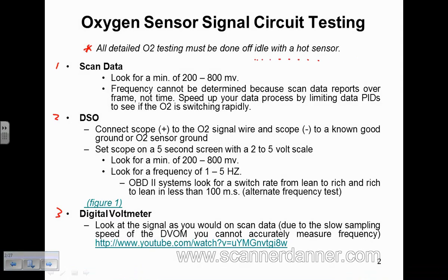Let's say here's your 800 millivolt line, here's your 200 millivolt line. It's okay if it goes above and below those lines. We just don't want to be inside of there. So if you're inside of that range, then that sensor is probably needing to be replaced. And you don't want to look at it with too much critique.